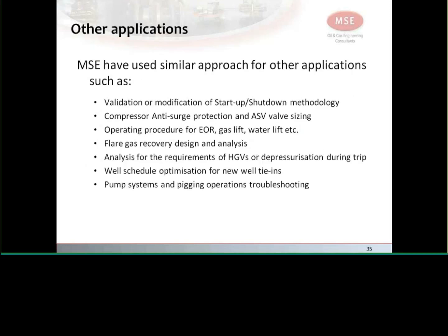We have used a similar approach for other applications, where we looked at the validation or modification of the startup and shutdown methodology for another existing asset that was coming back from redevelopment. They were bringing a new cluster of wells, a tie-in into the compressor that was modified, and so we simulated something like that, including the compressor and surge protection.